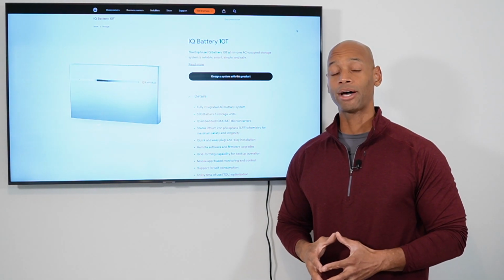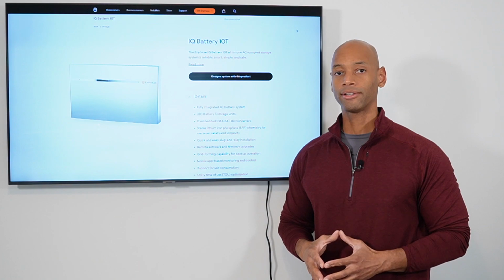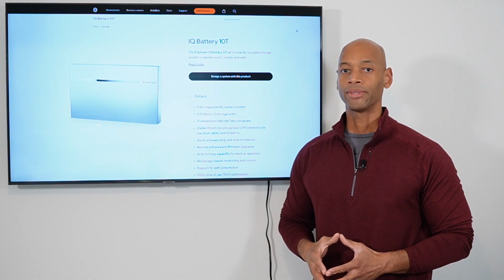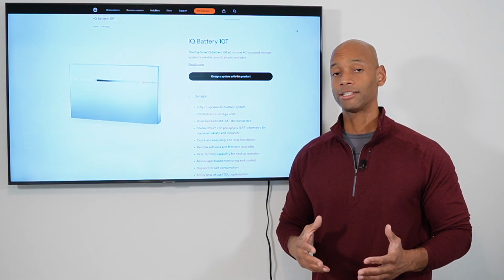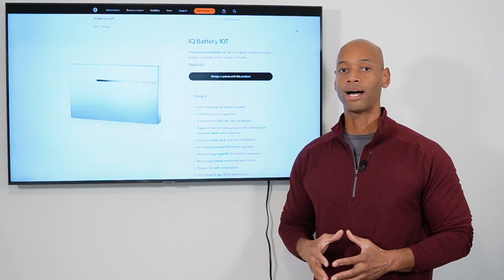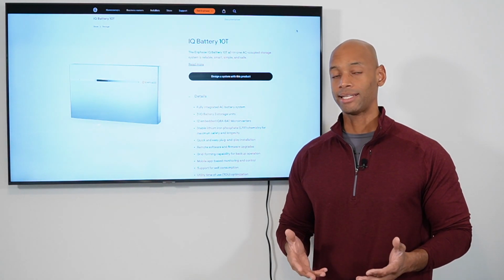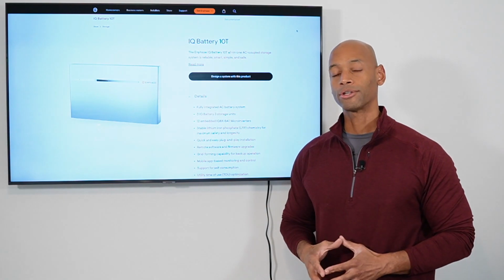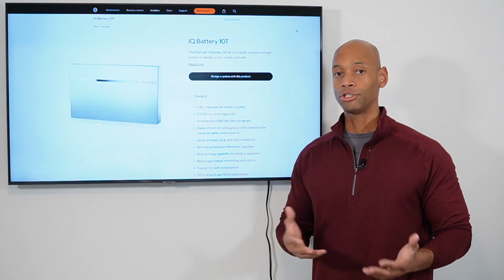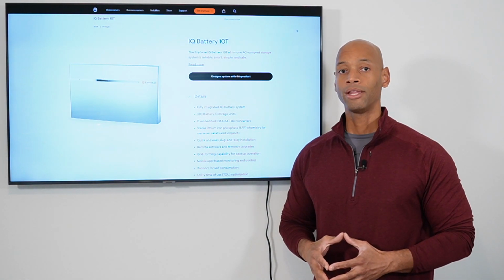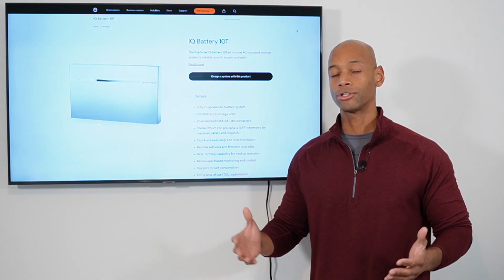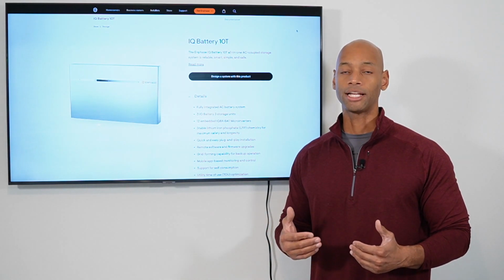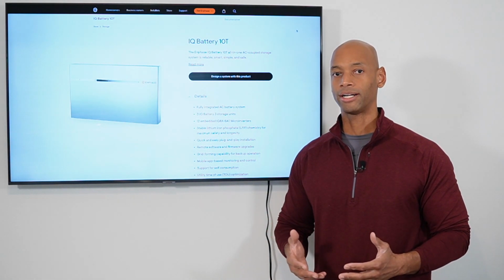Now, I should also say that using those microinverters internally does make Enphase really the most redundant system available. You've probably all heard about the advantage of a microinverter-based system on your solar array. It eliminates any central point of failure, right? So let's say one of the solar panels was damaged, you might lose power output from that single solar panel, but you're not going to lose the total system output the way that you would if you had a central inverter and the central inverter itself was damaged or malfunctioned.